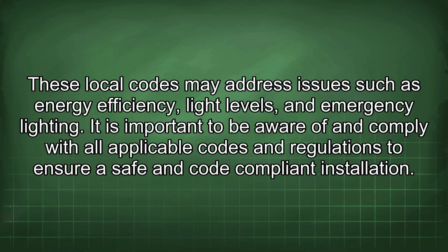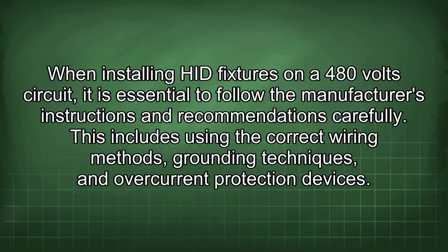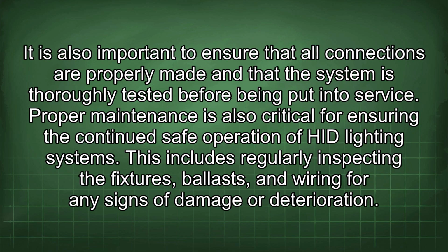When installing HID fixtures on a 480-volt circuit, it is essential to follow the manufacturer's instructions and recommendations carefully. This includes using the correct wiring methods, grounding techniques, and overcurrent protection devices. It is also important to ensure that all connections are properly made and that the system is thoroughly tested before being put into service.